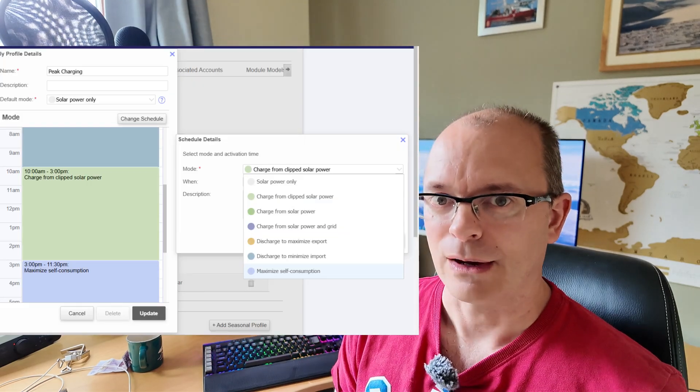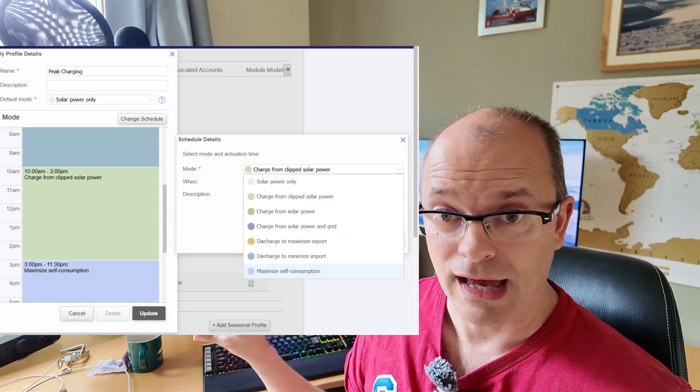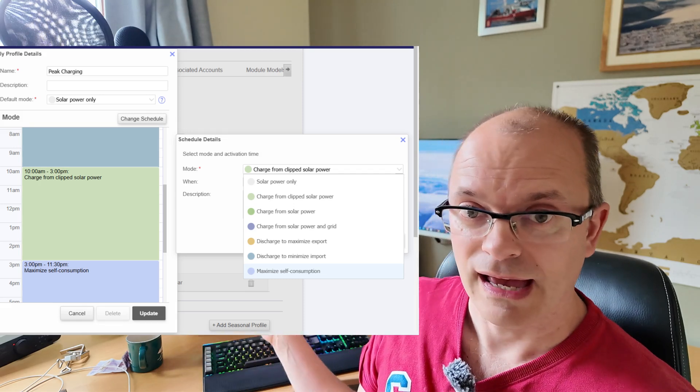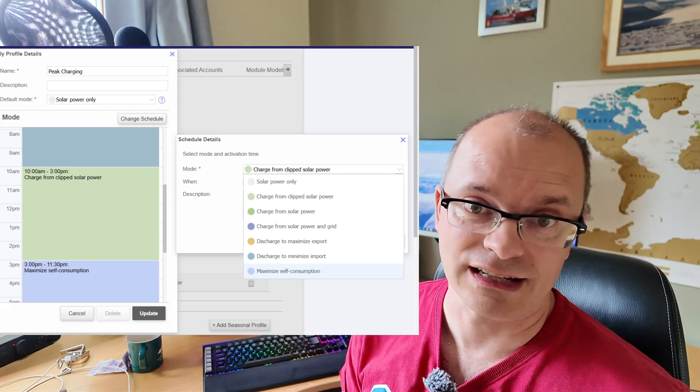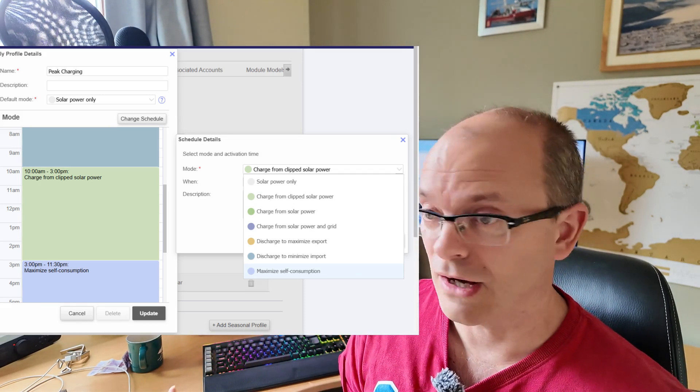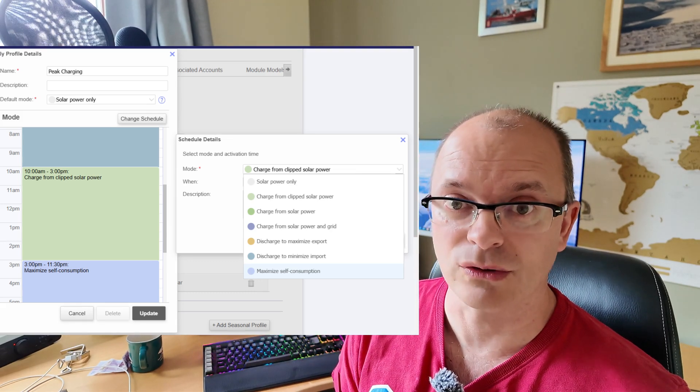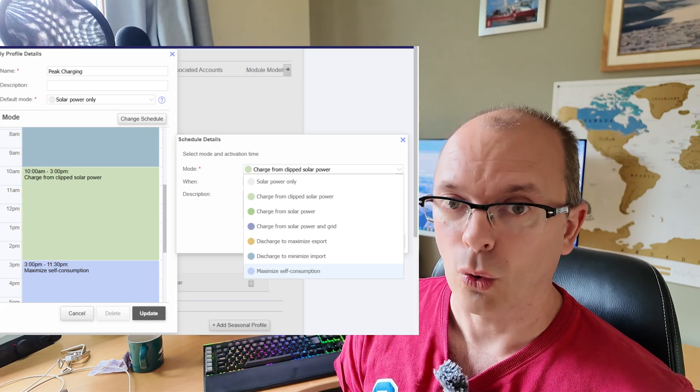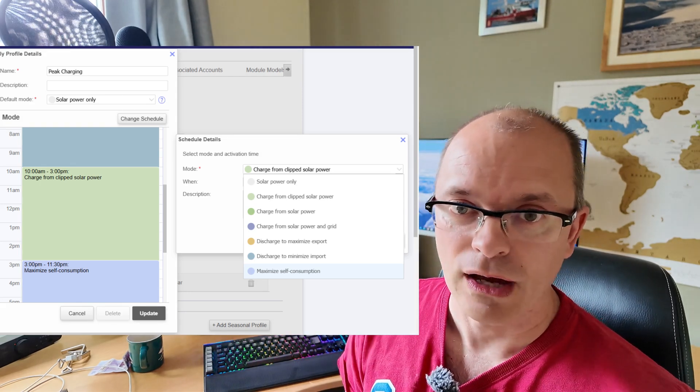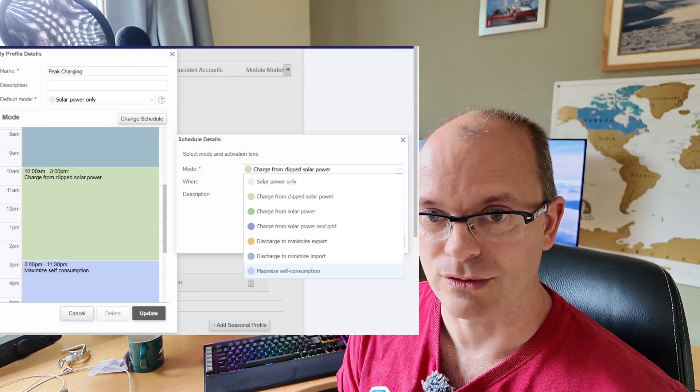Now we know that 6400 watts seems to be a hardwired limit for my SolarEdge inverter. I have sent the question to SolarEdge support, they might have a better answer than what I have managed to glean off the internet, but so far no answer from them is forthcoming. What I am going to say is that if you don't have a SolarEdge energy bank battery, you're out of luck. 6400 watts is what you have. If you do have a SolarEdge energy bank battery, then you can use that to your advantage to overcome this limitation. What you need to do is set the battery to charge up with peak solar. That will enable the SolarEdge inverter to produce as much electricity as it's allowed to produce, which in my instance is 5000 watts when exporting and 6400 watts when there is no export. All the remaining surplus can go into the SolarEdge energy bank battery.